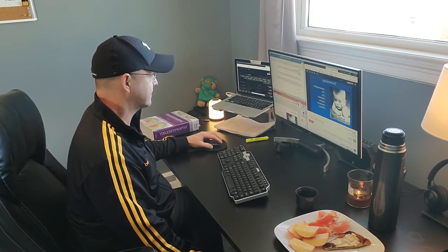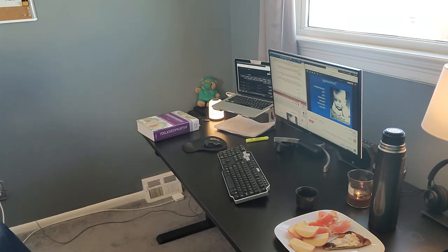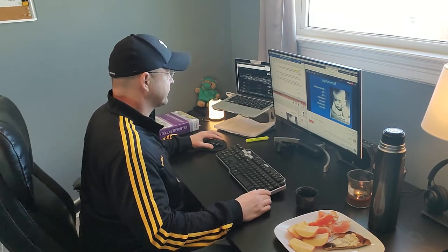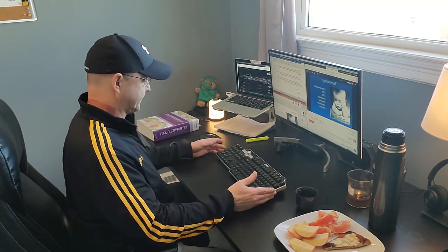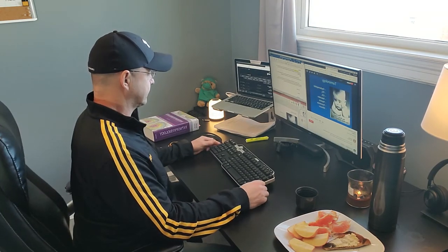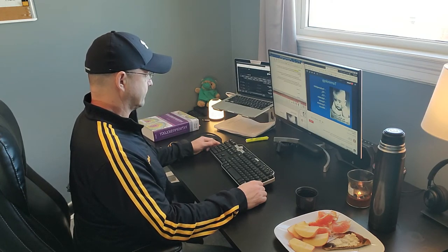It takes 60 to 90 seconds to do that calculation mathematically, to take that light that's been refracted back and to actually measure how many of the four hemoglobin sites are bound, exactly what the saturation is. So obviously our technology took this idea and really ran with it, minimizing the duration of time, the time lapse that there is in this measurement. And how did they do that?